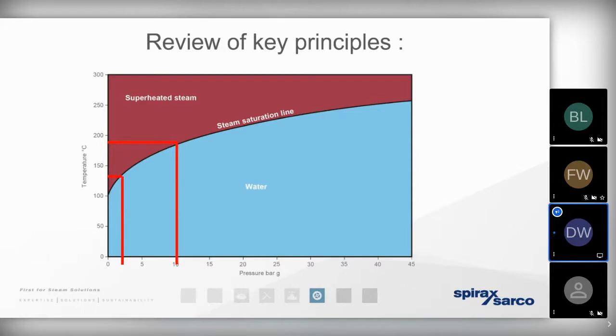That reminds us why it's very, very easy to control the steam output at the process by nothing more than manipulating the pressure. But the other thing that the pressure to temperature relationship demonstrates is the point at which steam gives up its heat energy and condenses. So if we've got any heat loss when the steam's under pressure, for example, in the distributing pipework, well, we know that the steam that condenses in the distribution pipework at 10 bar gauge, the temperature of the condensate is going to exist at the same point, 184 degrees.